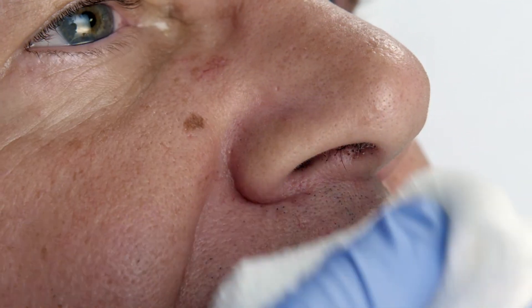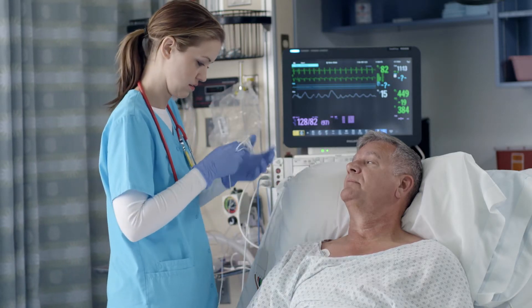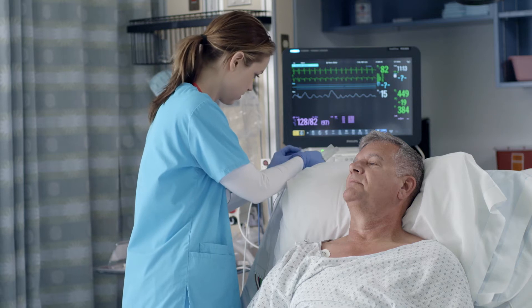Wiping the outside of the ALA and, if necessary, swabbing the inside of the nose to ensure clean contact is important for optimal performance. Once the site is prepped, use the provided applicator to apply the sensor to the ALA on the back part of the nostril toward the cheek.